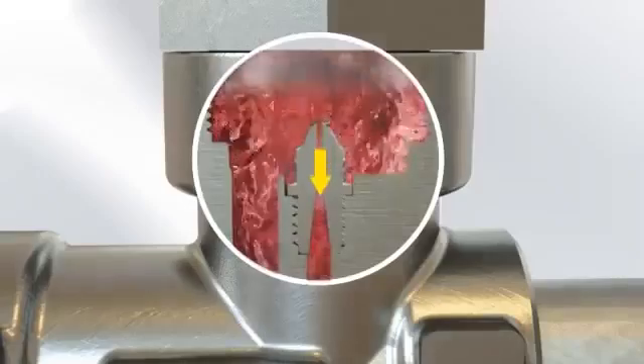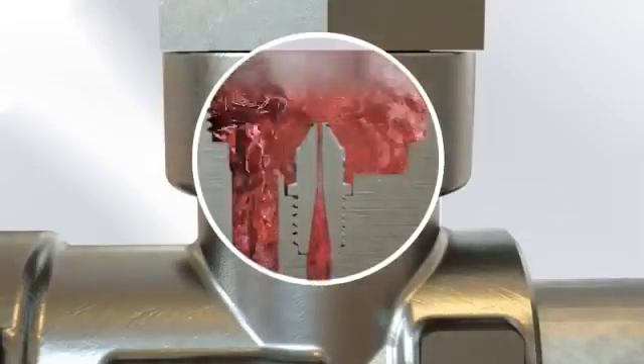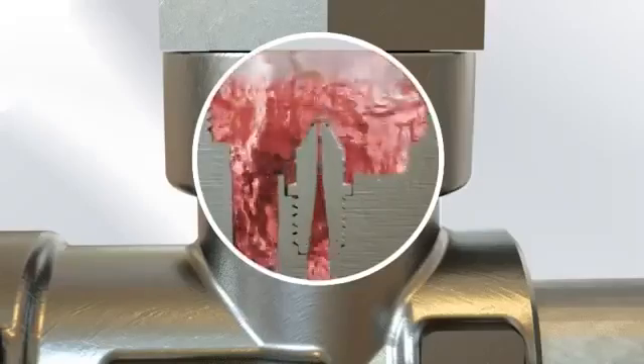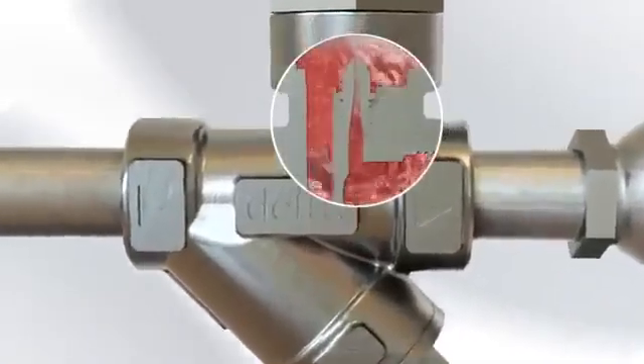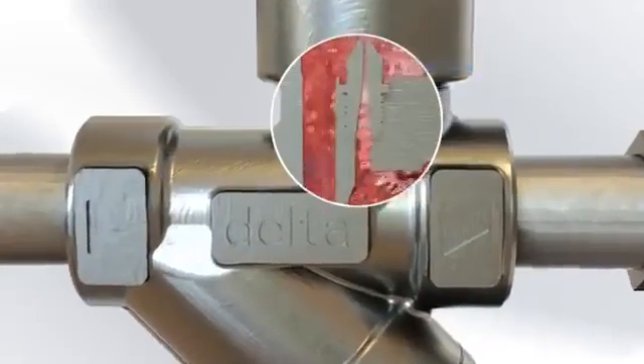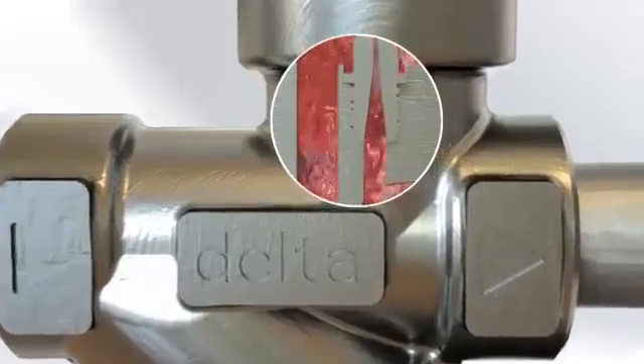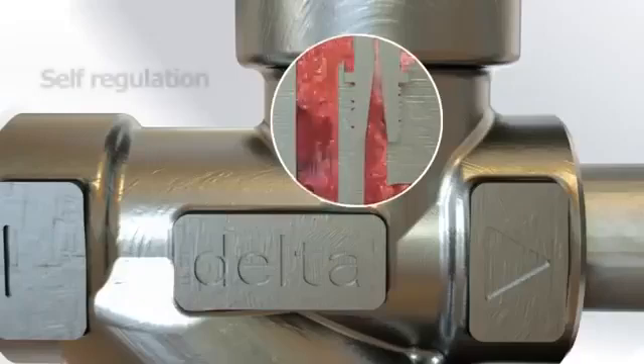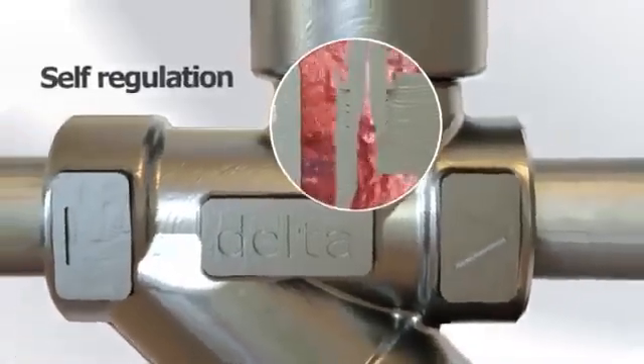This flashing creates a back pressure zone in the mouth of the Venturi. Because condensate is one thousand times denser than steam, it is able to push through this back pressure zone while restricting the steam. As the pressure and load in the steam system vary, so too does the percentage of flash steam being created at the mouth of the Venturi in the delta steam trap, which in turn allows the back pressure at the Venturi to vary accordingly. This varying of back pressure at the mouth of the Venturi allows the delta steam trap to self-regulate the condensate flow as the condensate load changes.